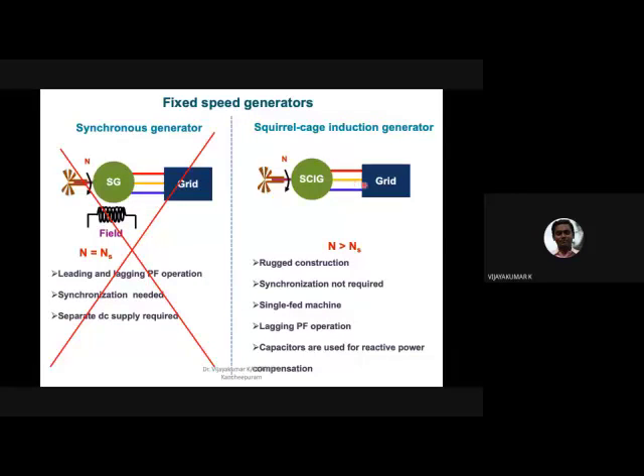And this is a single fed machine. In the synchronous machine it is double fed, I mean we have a field and we have an armature, so two types of supply. But here it's a singly fed machine. That means you can access only the stator coils. The rotor is shorted, the rotor is copper bars that are shorted inside, so you need not access the rotor coils. Here only the stator coils. So for handling purposes, this machine is easy.